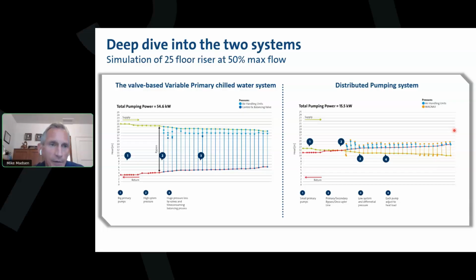What I'm showing on the left, this is a 25-floor building, and it's a building operating at 50% of max flow. We know that we spend most of our time operating at 50% or below. And on the left is a variable primary system, and on the right is distributed pumping.